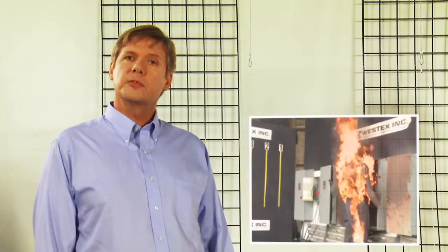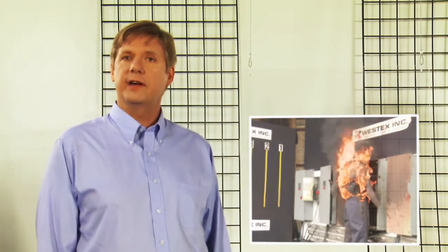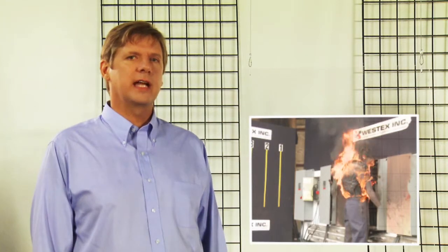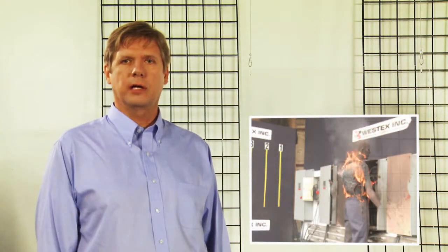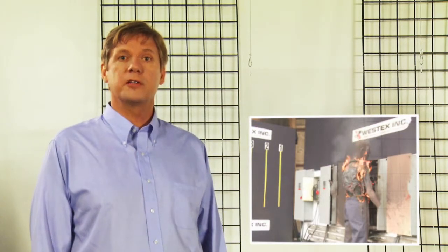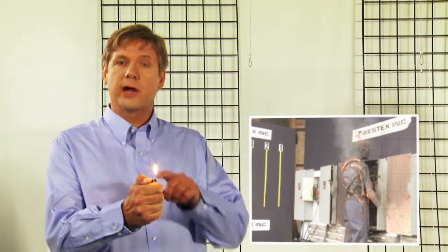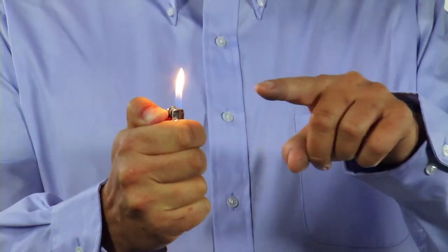As you can see, a worker exposed to an arc flash accident is likely to have conventional workwear catch on fire and has the potential of sustaining a very significant burn injury. The onset of second degree burns will occur at approximately 1.2 calories per square centimeter. This is equivalent to holding your finger over the tip of a flame of a cigarette lighter for one to two seconds.